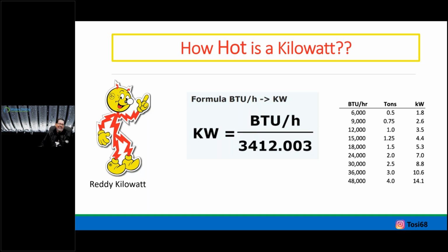So I jokingly have this thing like, how hot is a kilowatt? We're so focused on temperature, because I can't believe lowering water temperature. I'm not going to be that guy. I don't want the phone calls. I don't want people complaining. Well, your heat loss proves what you need to deliver. And that's not temperature. We're not delivering temperature. Every foot of baseboard has a BTU rating. This room requires 2,000 BTUs. So how hot is a kilowatt?